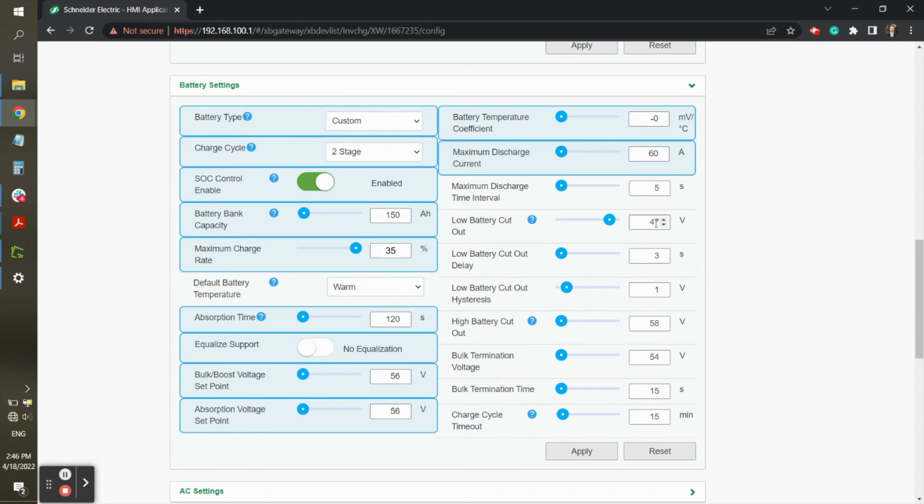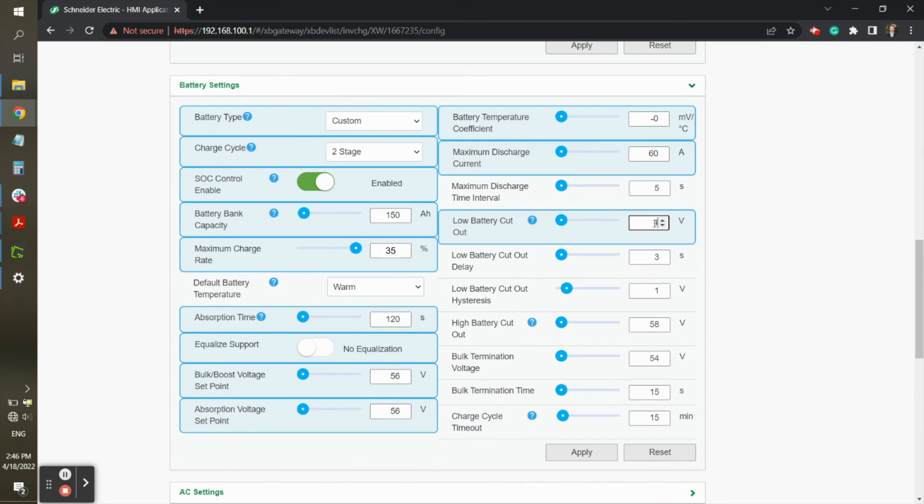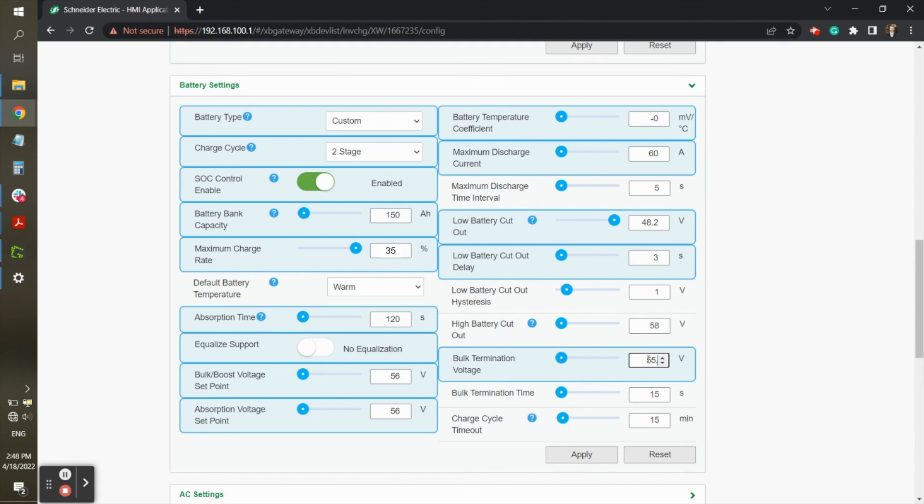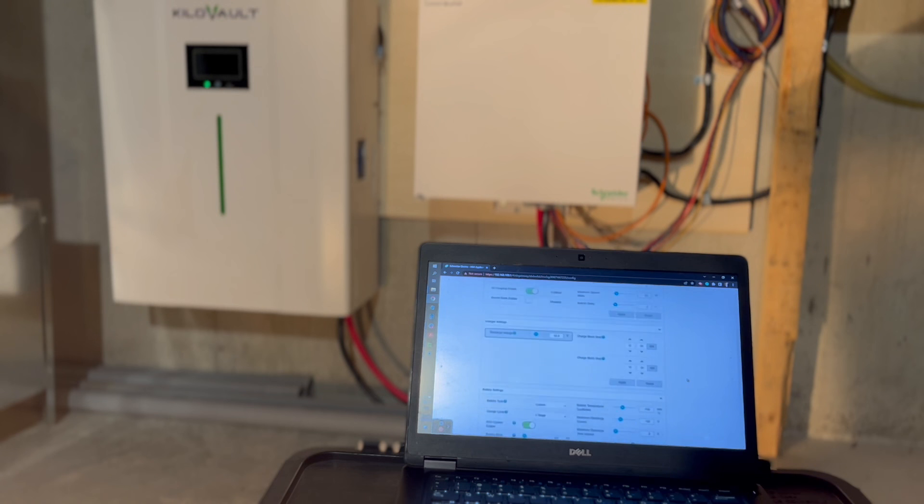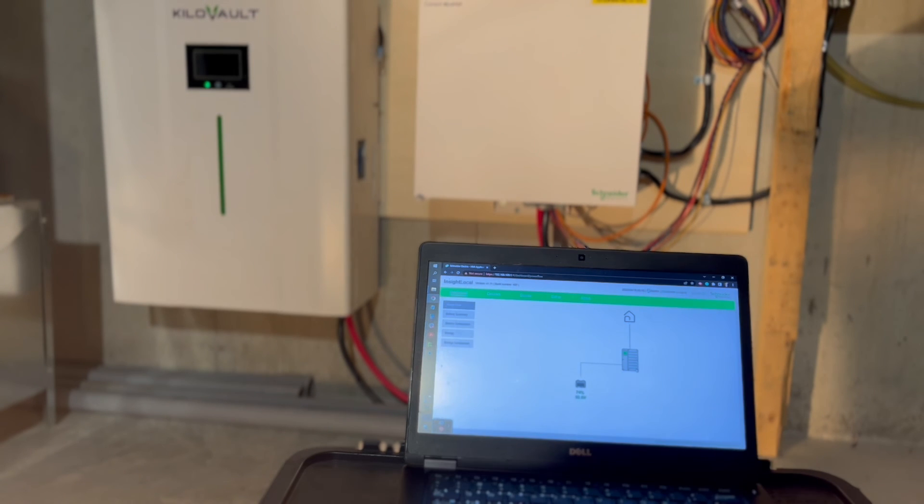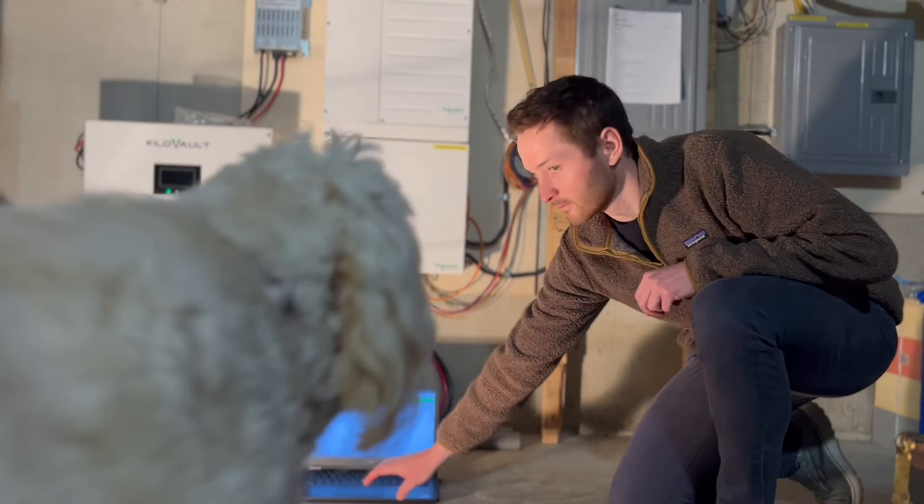Low battery cutout should be set to 48.2 volts, and low battery cutout delay to 3 seconds. High battery cutout can be set to 58 volts, and bulk termination voltage can be set to 55.2 volts. Press apply, and your settings will be saved to the XW inverter, and at that point you should be good to go.